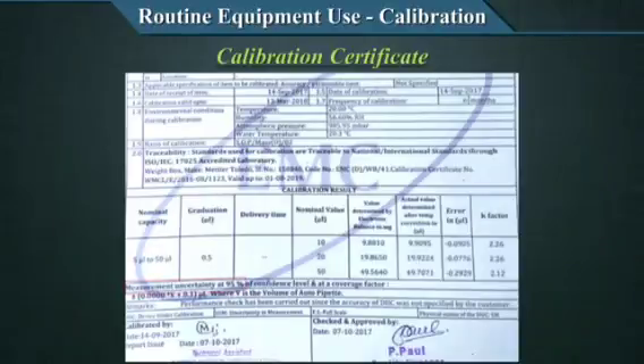This uncertainty here depicts the uncertainty your equipment has. Okay, I hope you are understanding it from the uncertainty that is specified earlier. That was the uncertainty of the standards. And now they are saying after calibrating, this is how much uncertainty your equipment is having. Coverage factor or confidence limits of each level, validity of the latest calibration and when the next calibration is due. So these are the components that generally are given on a calibration certificate.